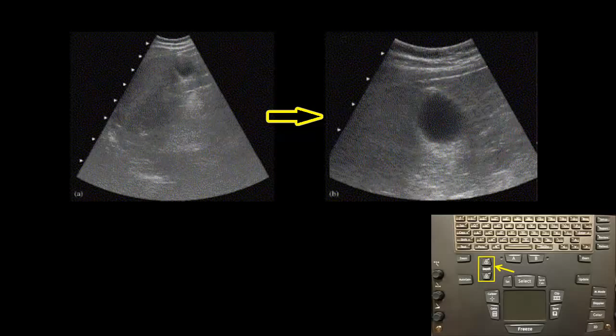As changing the depth may impact how future settings affect the image, getting the target tissue in the center of the screen should be your first step when scanning. For a guide, there are hash marks on the left side of the screen representing stepwise increments that vary depending on which probe is used. At the bottom right-hand corner of the screen, there's the total depth indicated in centimeters.